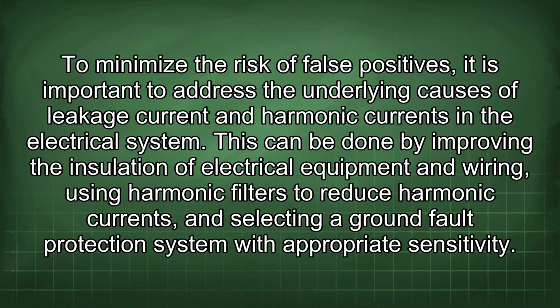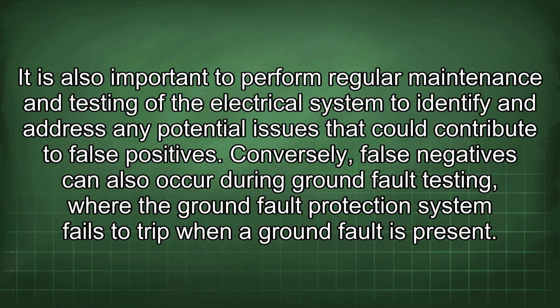Therefore, it is important to select a ground fault protection system with appropriate sensitivity for the specific application. To minimize the risk of false positives, it is important to address the underlying causes of leakage current and harmonic currents in the electrical system. This can be done by improving the insulation of electrical equipment and wiring, using harmonic filters to reduce harmonic currents, and selecting a ground fault protection system with appropriate sensitivity. It is also important to perform regular maintenance and testing of the electrical system to identify and address any potential issues that could contribute to false positives.